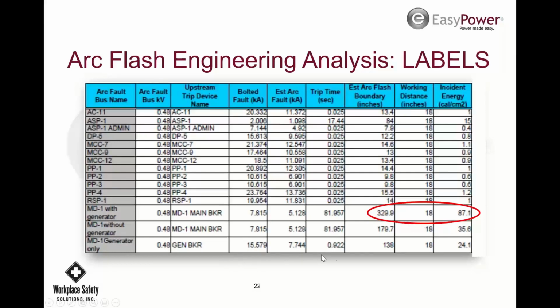And then the generator only is now, that's got a reasonable clearing time, and it's 24 calories per square centimeter, so it's reasonable. The thing that's really quite bad about this is 3 different scenarios, and all of this will be impacted by these 3 different scenarios. So there should be 3 spreadsheets, total spreadsheets for all 3 scenarios. So whatever the scenario is, you can go into it and see where you're at.